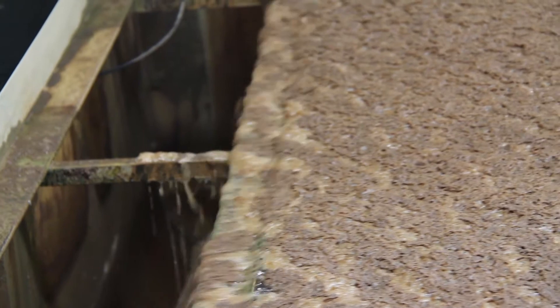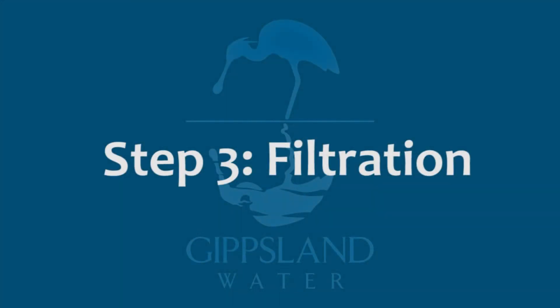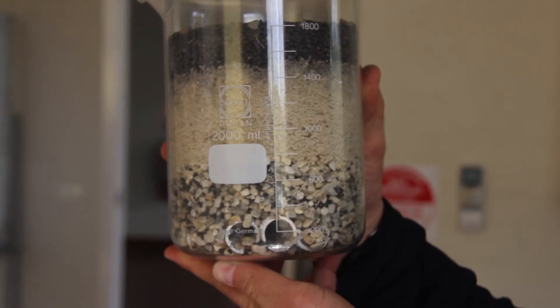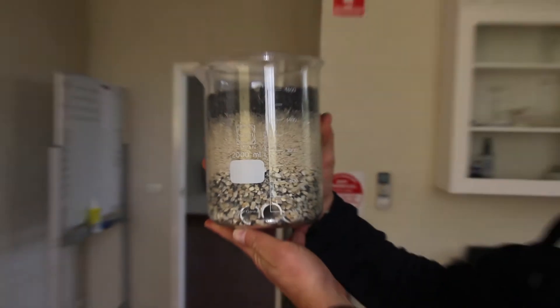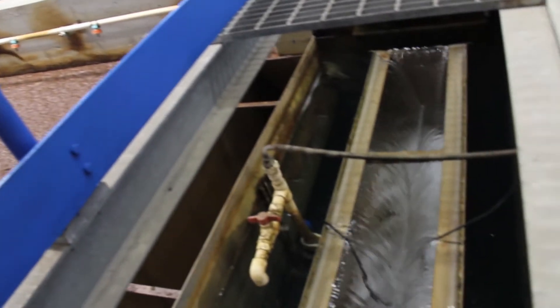The vast majority of dirt is removed in this part of the process. After separating the solids, the water is sent on to the filtration step. Filtration involves running the water through a large filter made up of sand, gravel and coal. This removes the remaining floc particles that may have made it through the flotation and clarification processes shown earlier.